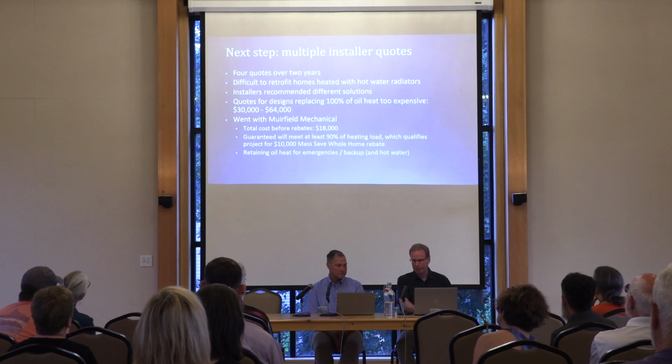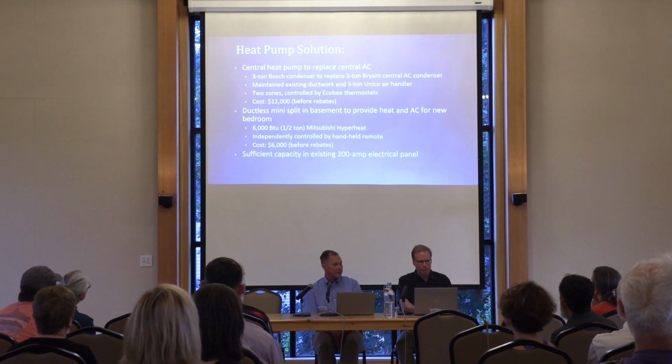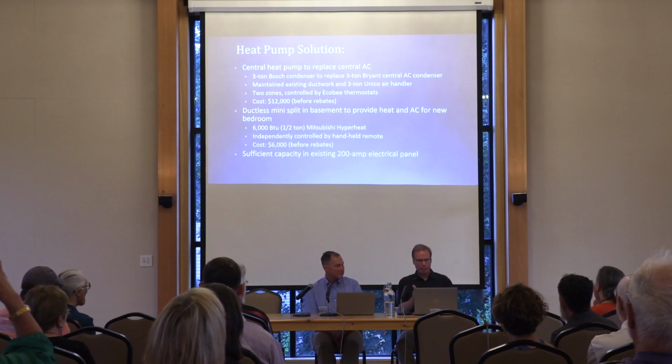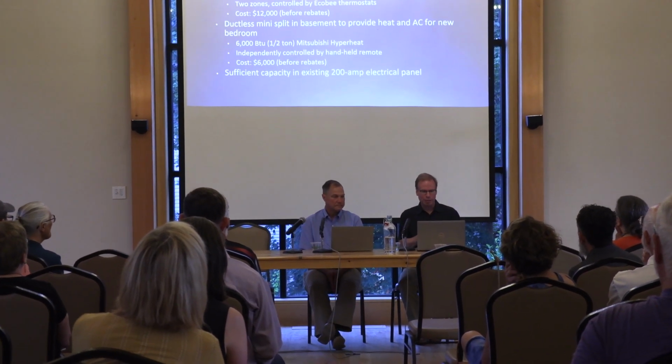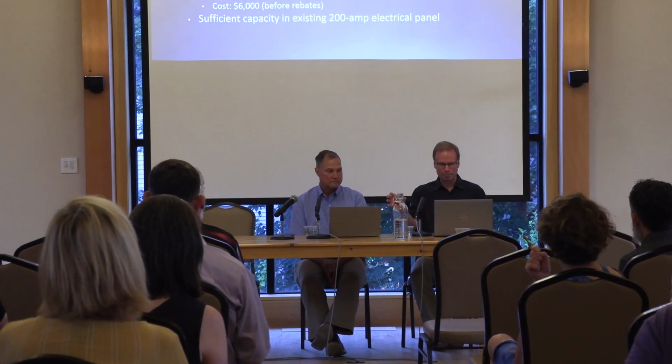And the total cost was $18,000 for that central heat pump system, which serves the main floor and the top floor of the house, but not the basement. So I was up before, and that was before the rebate, 18,000? 18 before the rebate. Okay. I had existing ductwork, and I was able to reuse the air handler for the central AC. So we went with a 3-ton Bosch condenser, which is the outdoor unit, to replace the 3-ton Bryant central AC condenser. Maintained the existing ductwork, maintained the existing 3-ton Unico air handler. Created 2 zones. One is the main floor, one is the bedrooms, controlled by Ecobee thermostats.